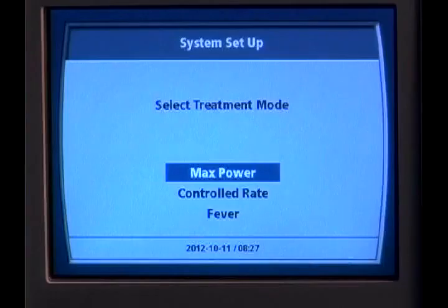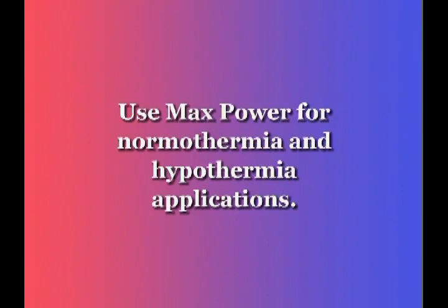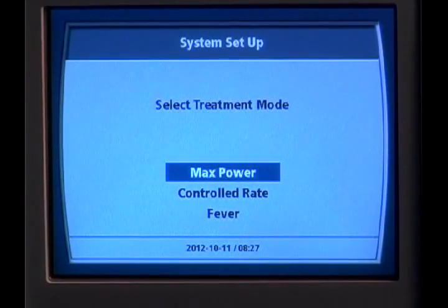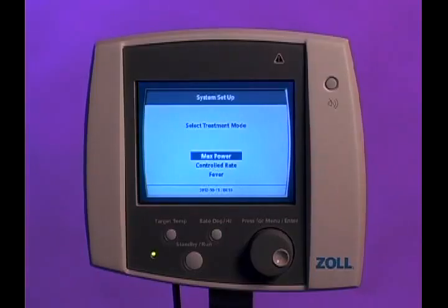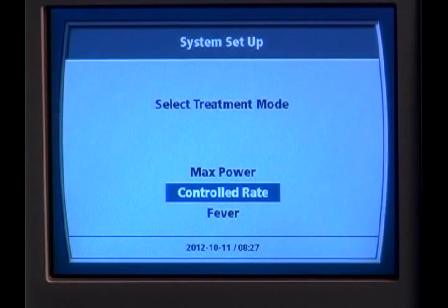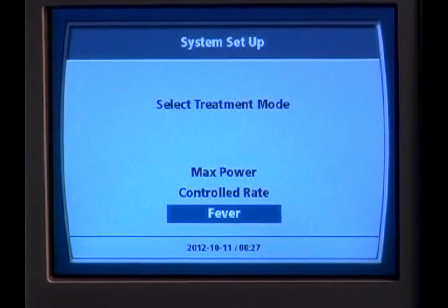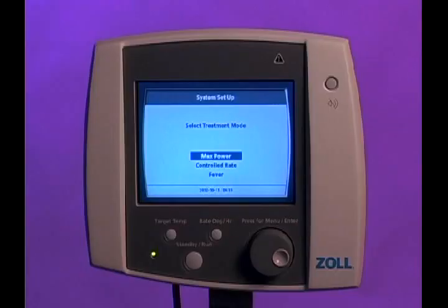Next, you're prompted to select Max Power, Control Rate, or Fever. The Max Power setting can be used for both normothermia and hypothermia applications. The Max Power mode should be selected when you want to cool or warm the patient very quickly. To precisely control the rewarming rate of the patient, the setting to choose is Control Rate. Fever mode is used for controlling fever and maintaining normothermia. Any of these settings may be changed at a later time if required. Please note, during therapeutic hypothermia applications, never choose the fever mode.